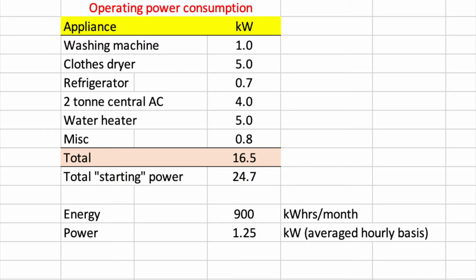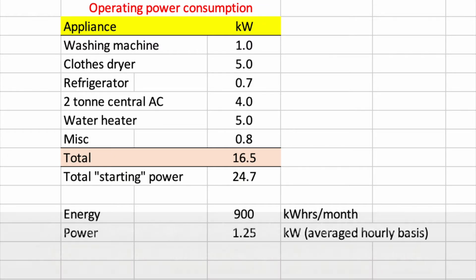Kilowatts is the power requirement, not an energy requirement. If you integrate, that is add up all the power over a certain period of time, you get the energy consumed. One thing to note with electrical motors is that they require a surge current when they start up, so you typically have to account for that. The total starting power, if all these appliances were turned on at the same time, would be about 25 kilowatts. But that's not usually the case, since they operate in an asynchronous and staggered manner, so typically you won't ever reach that kind of power level.